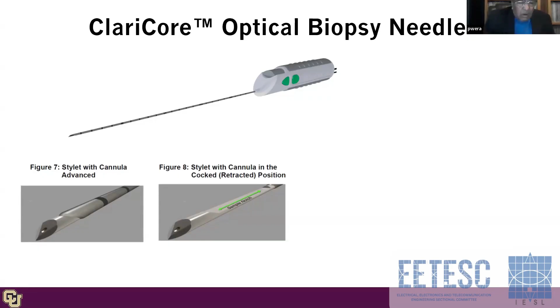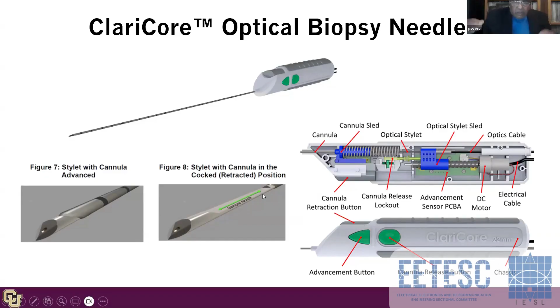And here is, there's a stepper motor inside the handpiece that will advance the inner needle in steps of 1 millimeter. I'll show you a video once we get there. Once you have gone through the length of the prostate, 18 millimeters into the prostate, you press the button, and the outer needle will come and cut a tissue piece, the one that you measured and classified. So the outer needle is the cutting mechanism. If you go back here, you can see this will cut the piece of core, and then there's a little notch here, the sample notch we call it. The core will be in there, and then you take that to the pathologist.